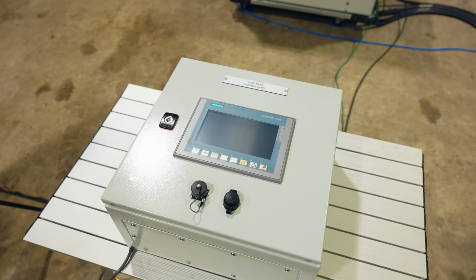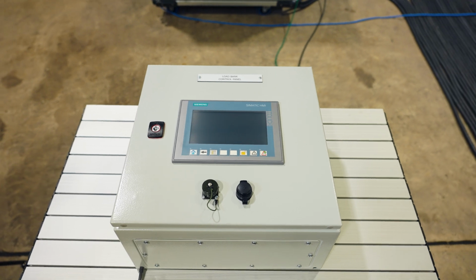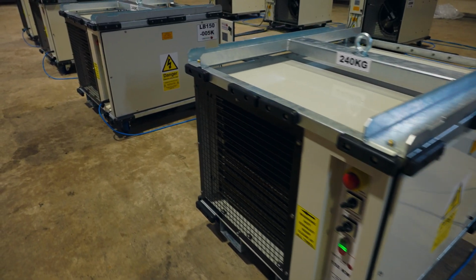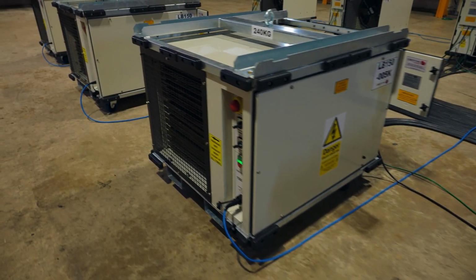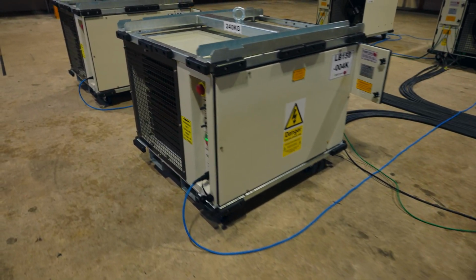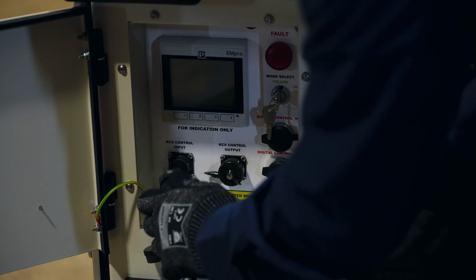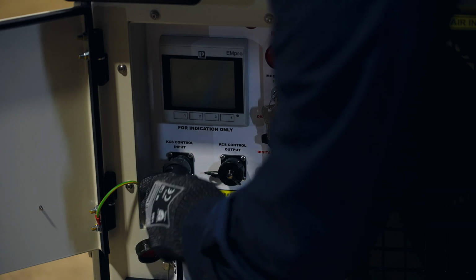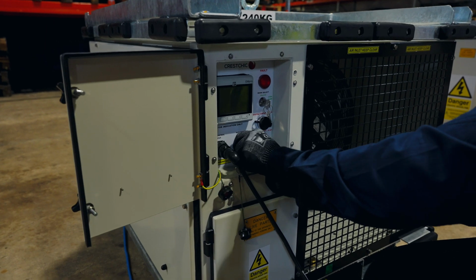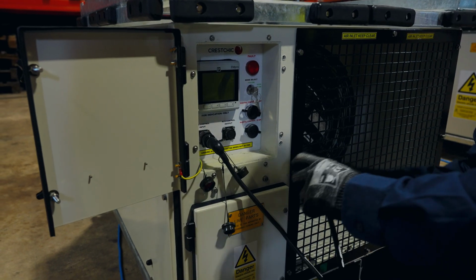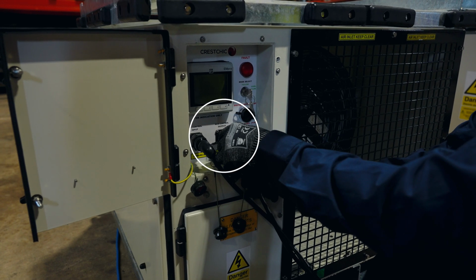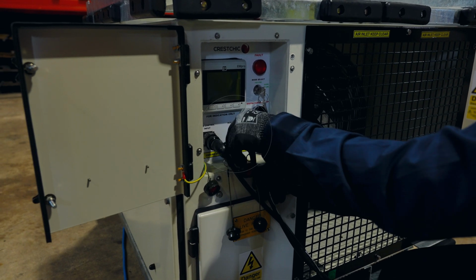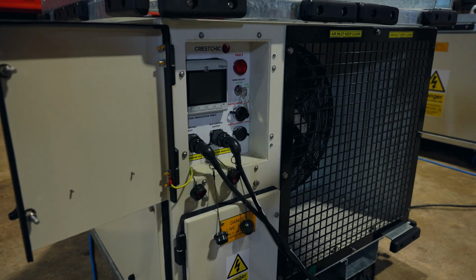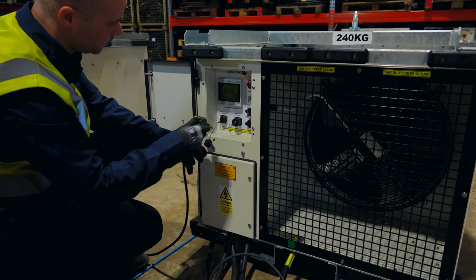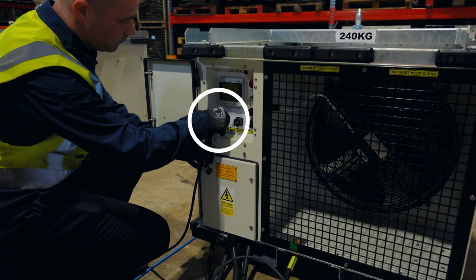The other method of controlling the load banks is with Crestchic's digital controller. This is primarily designed for using multiple load banks connected together and being controlled from this one controller. Much in the same way as the KCS controller, the digital controller is connected into the control input of the first load bank, then a control cable connected from the control output of this load bank into the control input of the next load bank, and this is then repeated on the rest of the load banks until they are all connected.